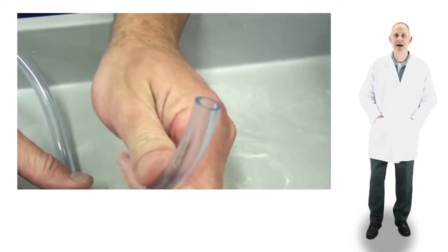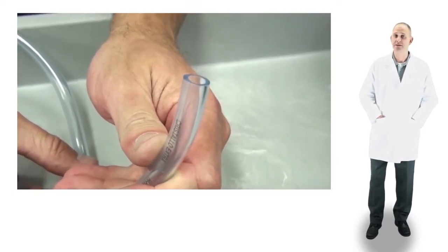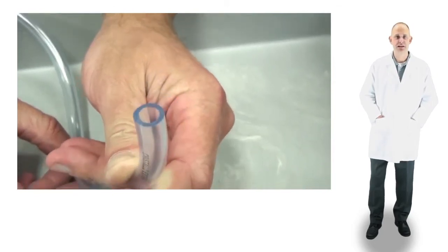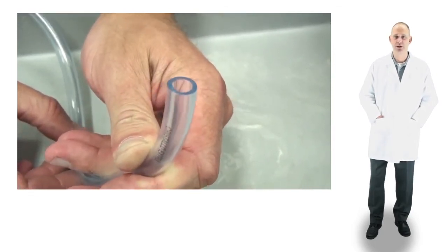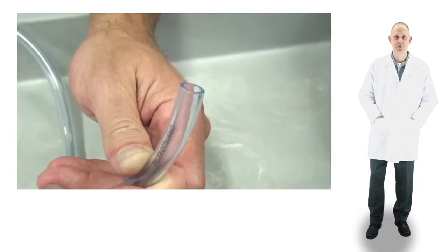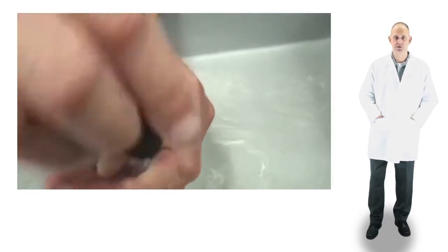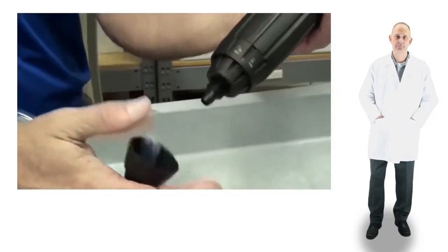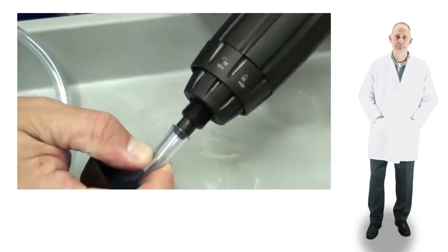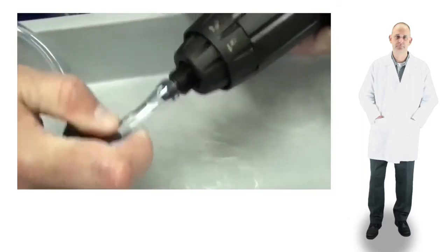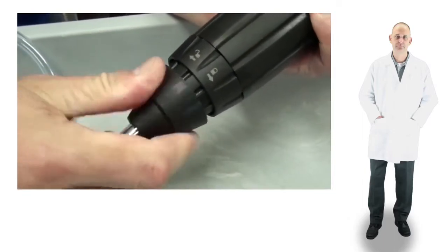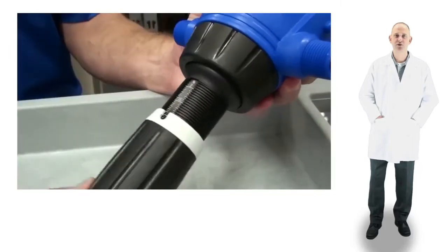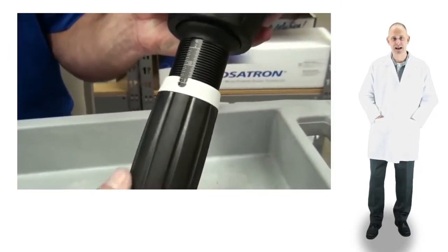One last thing. Take a look at the top of the suction hose. If it flares out, cut an inch or so off and reinstall. Or, if the suction hose is cracked, rigid or looks really old, just replace it. Thread the suction hose nut onto the hose, slide it onto the barb and hand tighten the nut. Make sure to set your injector to the desired setting.